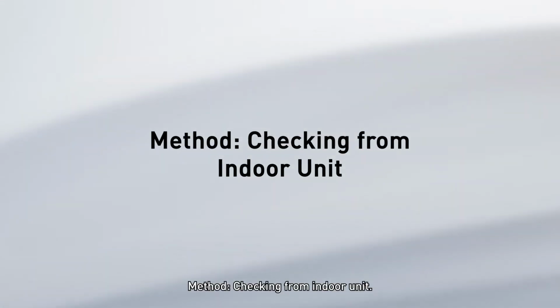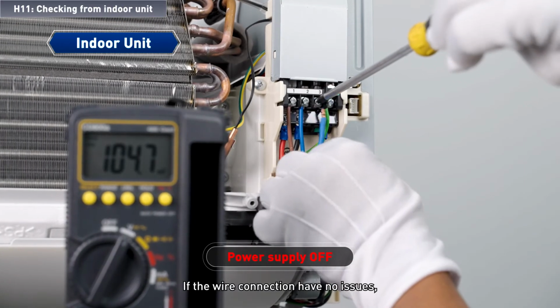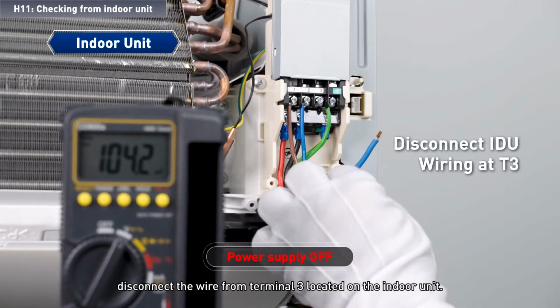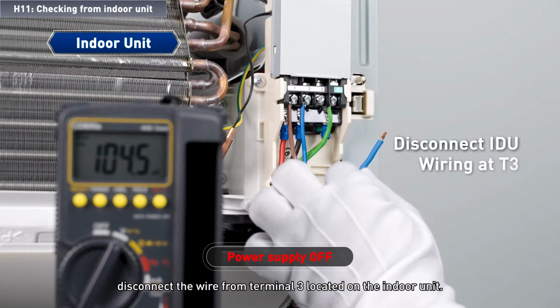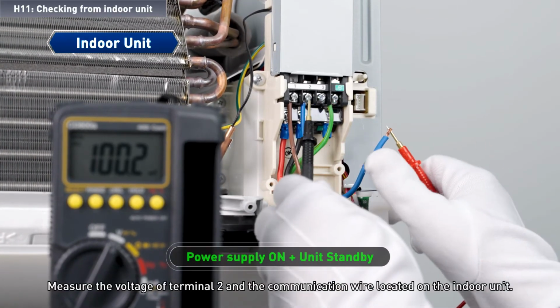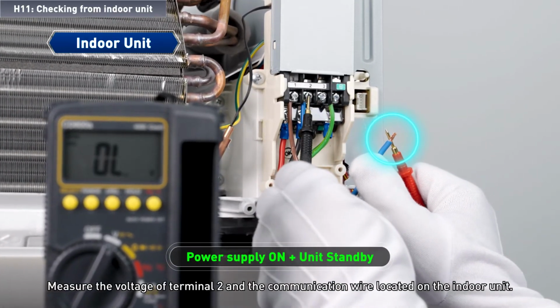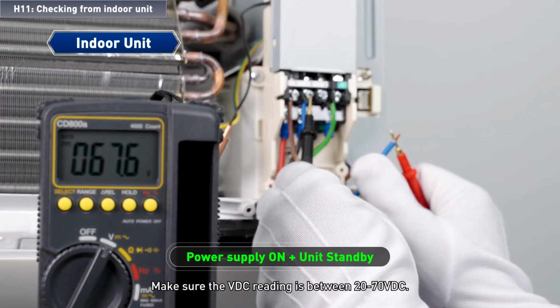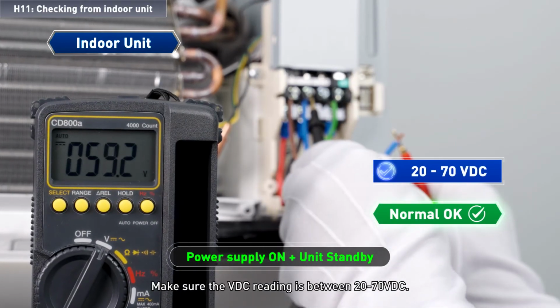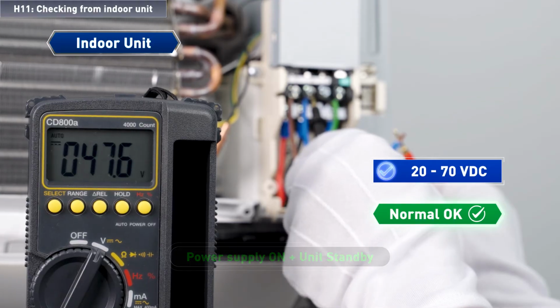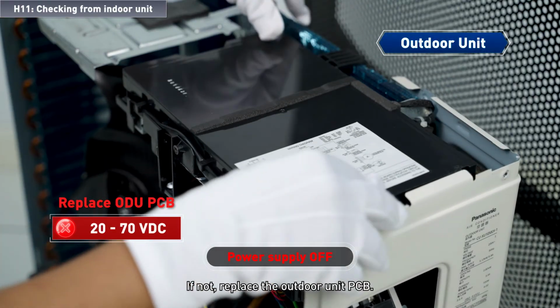Method: checking from indoor unit. If the wire connection have no issues, disconnect the wire from terminal 3 located on the indoor unit. Measure the voltage of terminal 2 and the communication wire located on the indoor unit. Make sure the VDC reading is between 20 to 70 VDC. If not, replace the outdoor unit PCB.